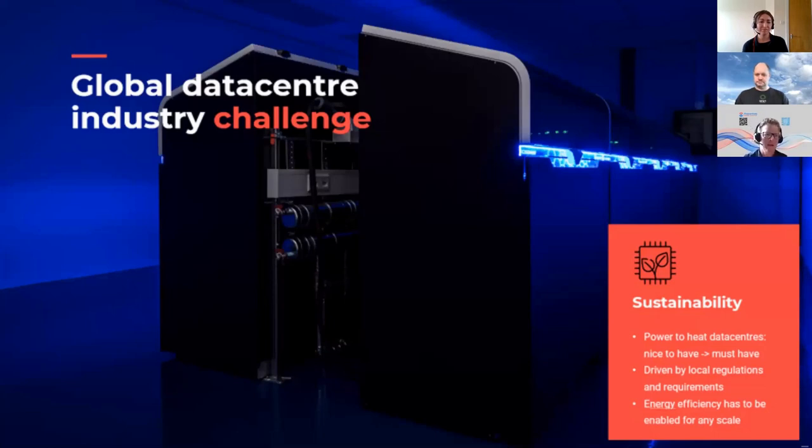Alex already mentioned the energy reduction that it has in the immersion environment due to the lack of fans and pumps and so on. But also the other thing to bear in mind is the stability of the environment. So the cooling in immersion, when the power load is varying up and down, the stability that it brings really is going to give it the longest life possible. So that I think is a great combination.